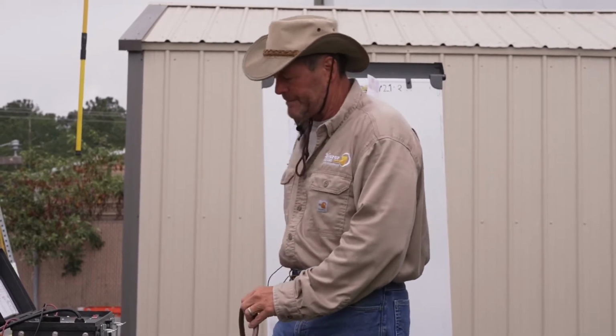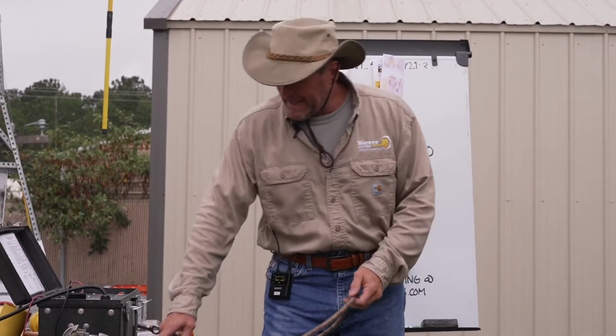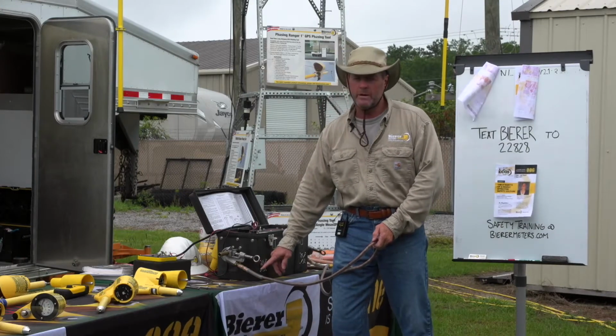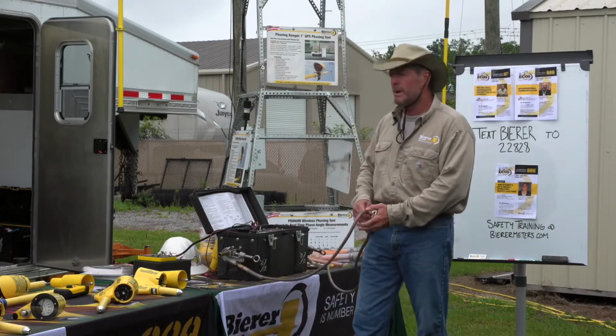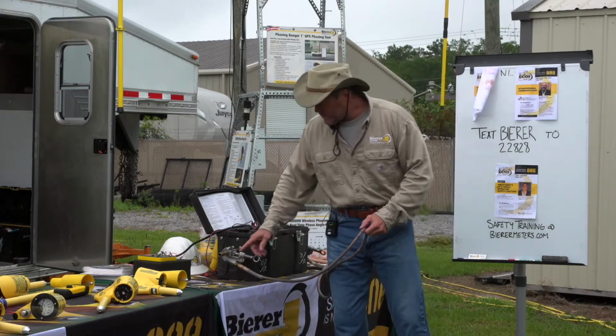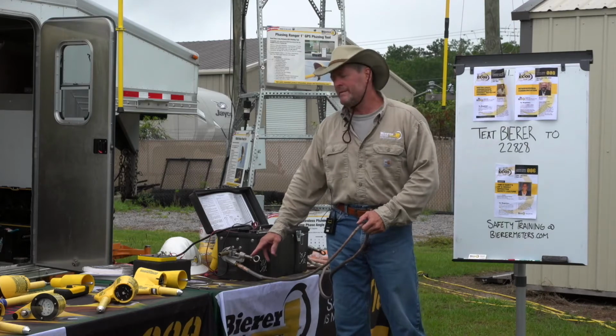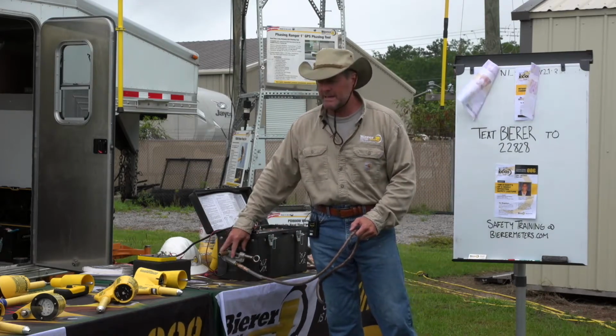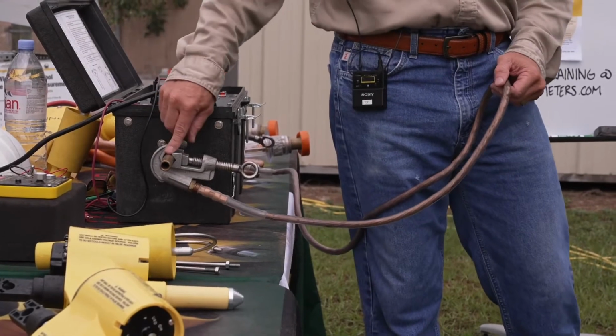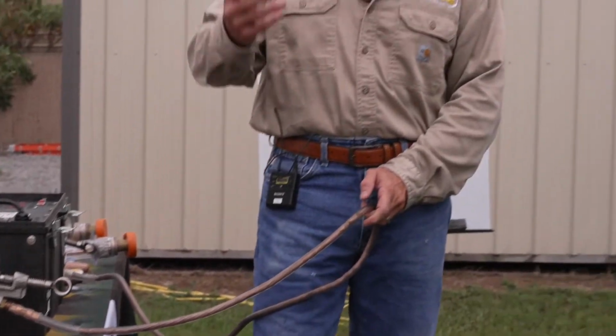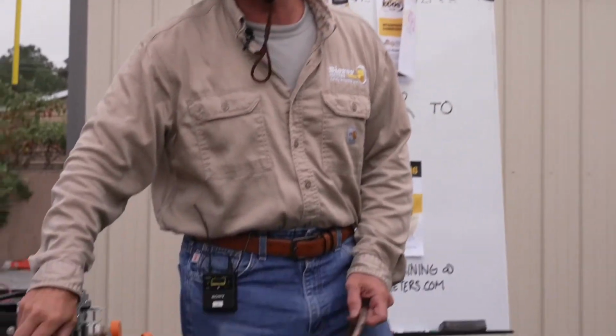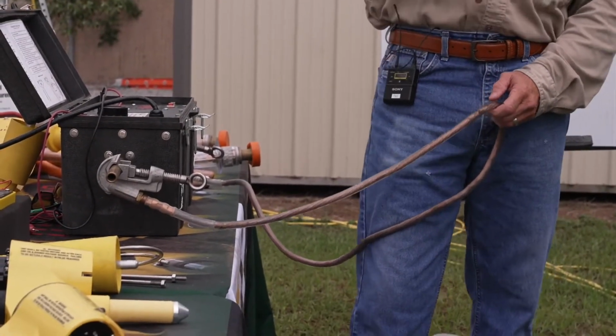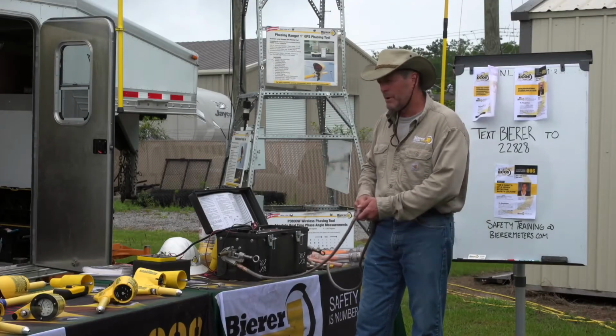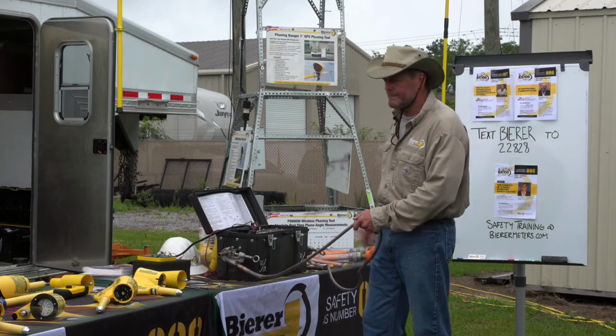So you're going to visually inspect. You're going to look for a lack of blackened copper if you can see the copper, a lack of patinaed copper. You don't want to see any bubble jacket, any cracks on your clamps, any obvious loose connections, or any oxidization on your components, especially on your contact points—and this is crazy because I've seen it walking into these utilities. So when you're setting up your EPZ and bracketing, make sure your contact points are clean on both your equipment and your TPGs.